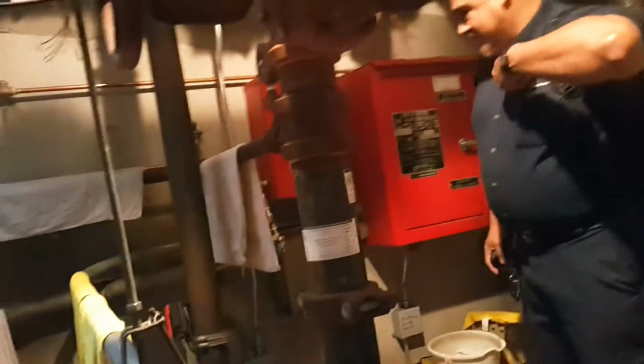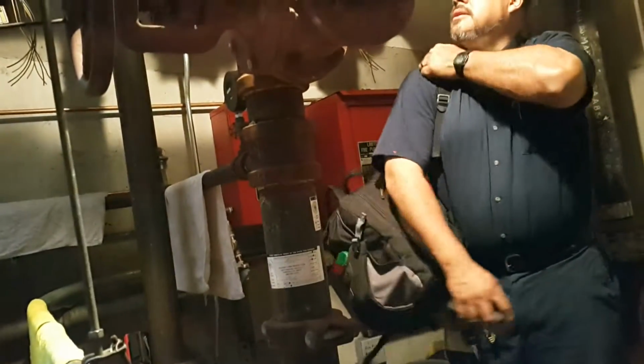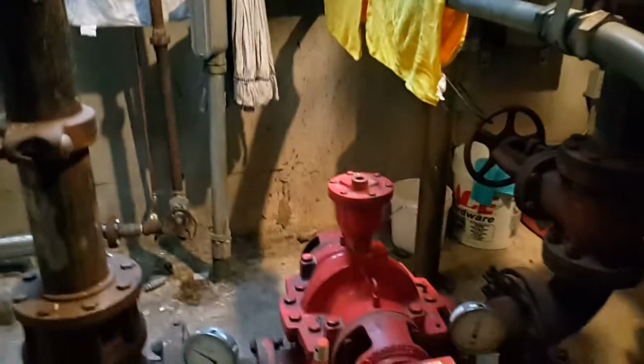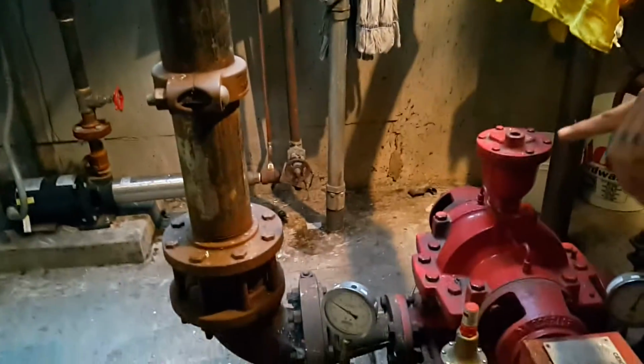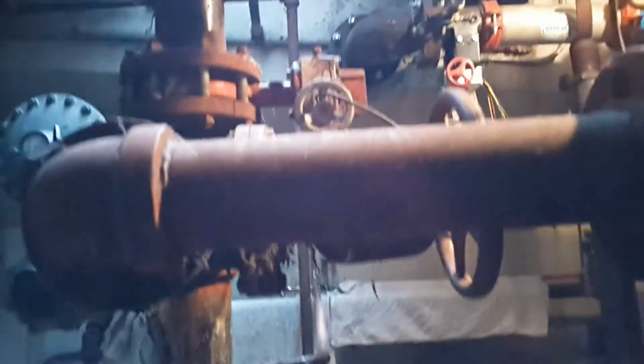Stuff in there. Alrighty, so first thing we gotta do is check our directional flow of the fire pump. So we look at it, our discharge valve is that one right here. So the water comes in from the city, comes around, goes down this way to the fire pump, and goes up to the building. This is called a flow meter loop. This is how we test the fire pump flow.